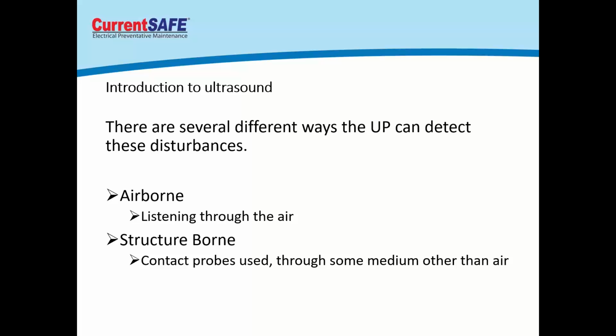One thing to keep in mind when using the ultra probe in the field is that it's not rated for an electrical environment—it's not an insulated tool. So our technicians would never want to use a touch probe on anything that's open and energized; we'd always want to do that airborne style. The structure-borne approach is always for oil-filled devices, where we're not exposing technicians and electricians to energized work, because we never want to risk a shock or create an arc flash event and have somebody get hurt.